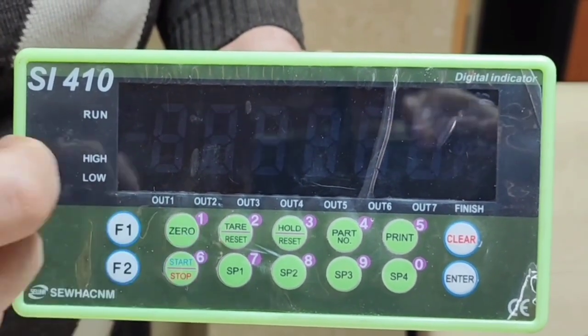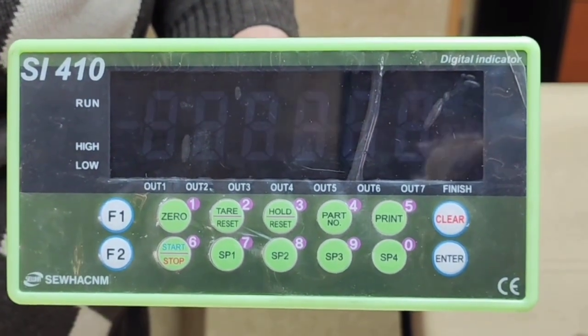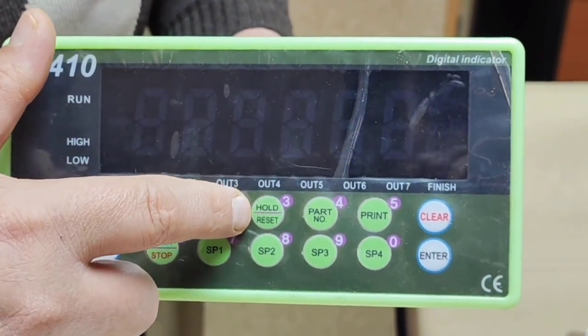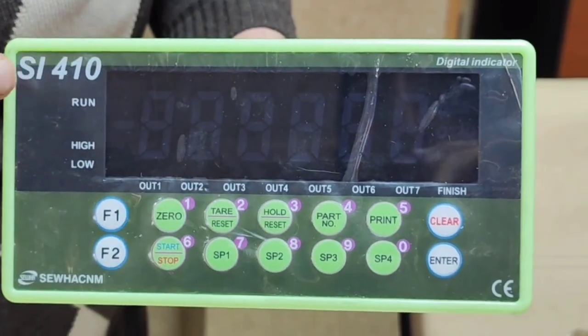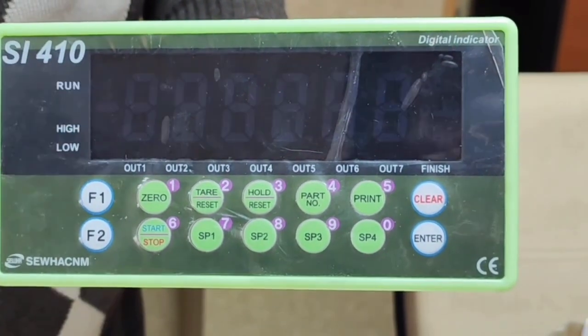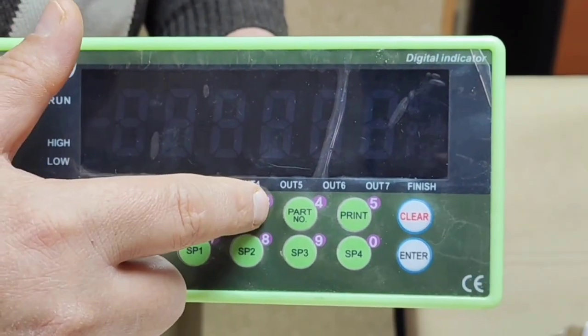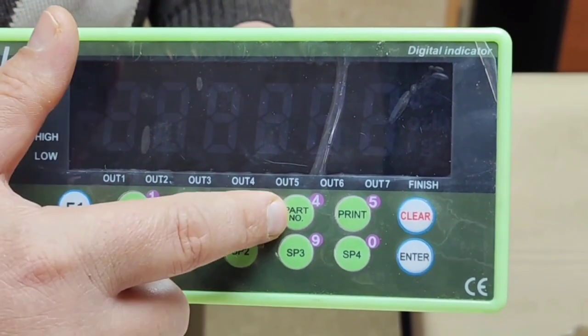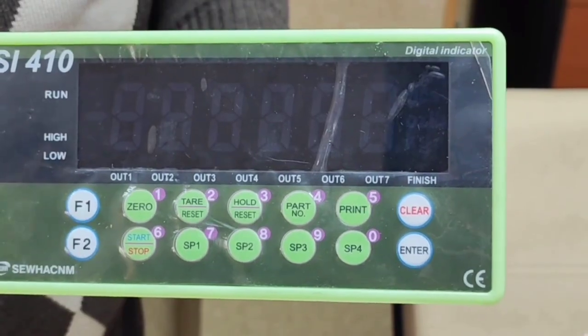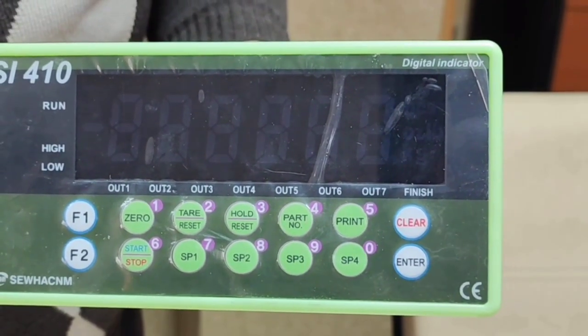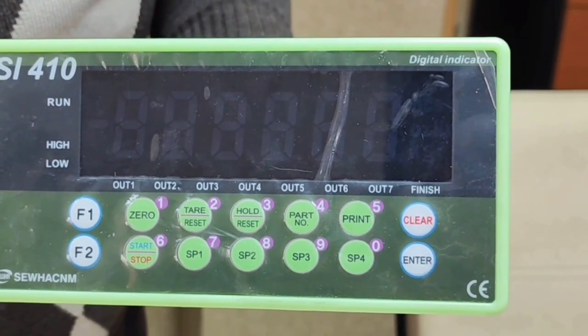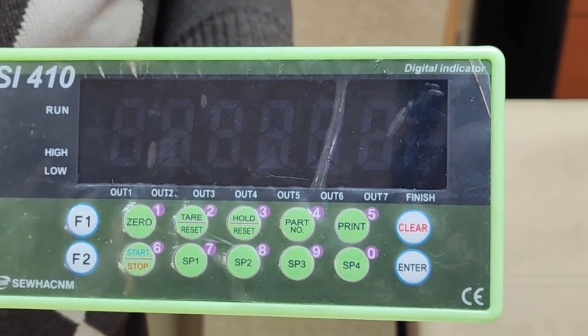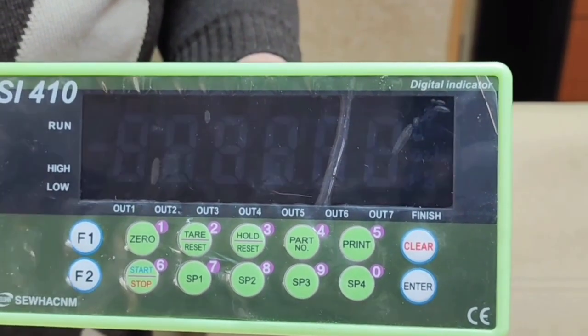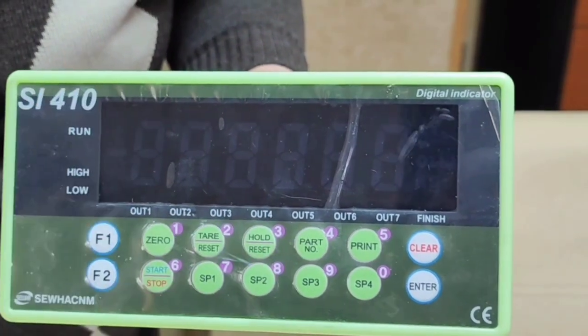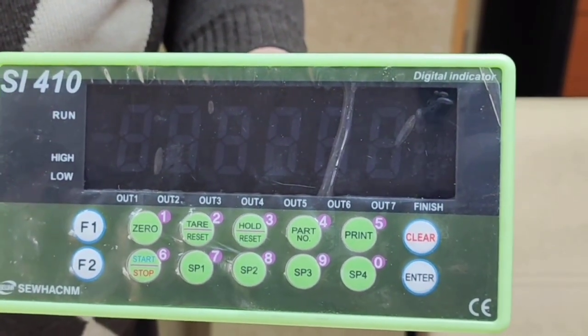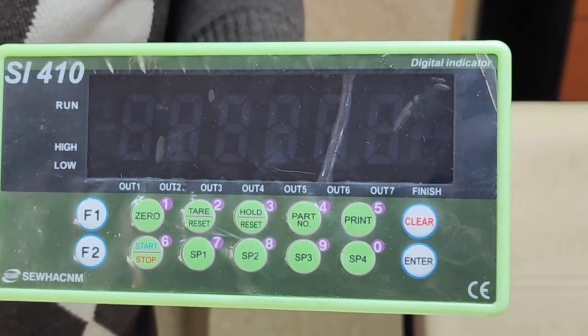We have a tare and tare reset button, which allows us to obtain the net weight of the item. There is also a hold and hold reset button. When we press it, the scale holds the weight for us, and when we press reset, it returns to normal mode. We have a part number button, which allows us to input formulas into the device. By formula, we mean the operation of the relays, and we can set different formulas for relay operation. In other words, we can save different set points under the title of part number. For example, part number 1, part number 2.